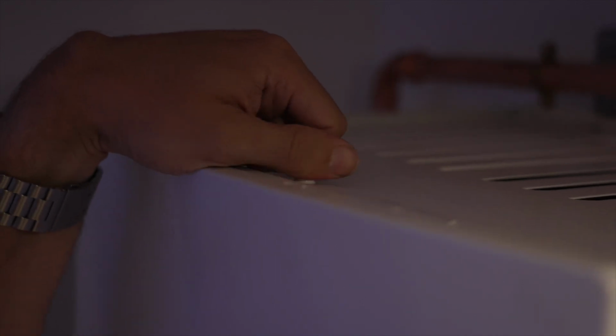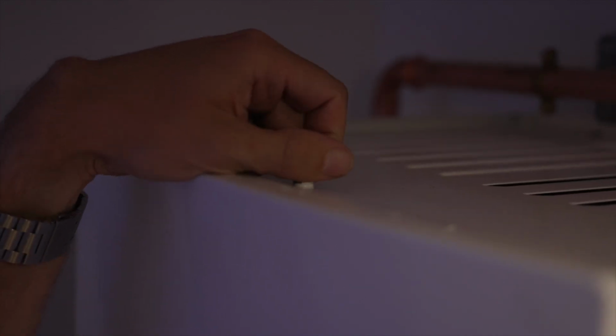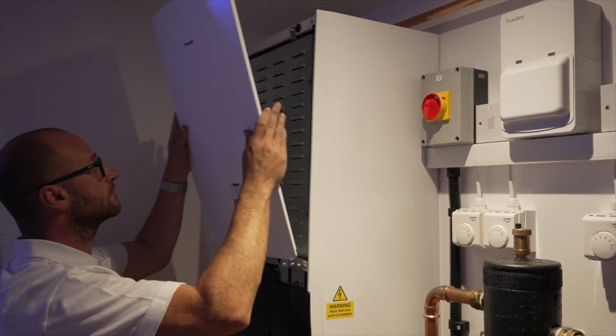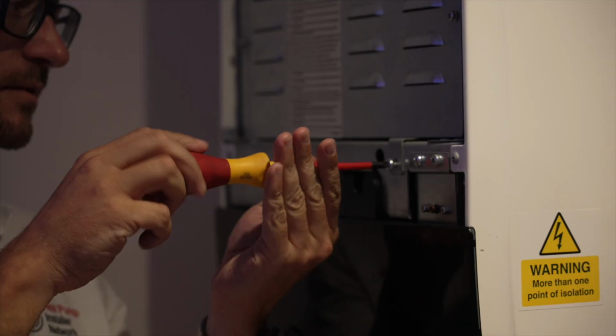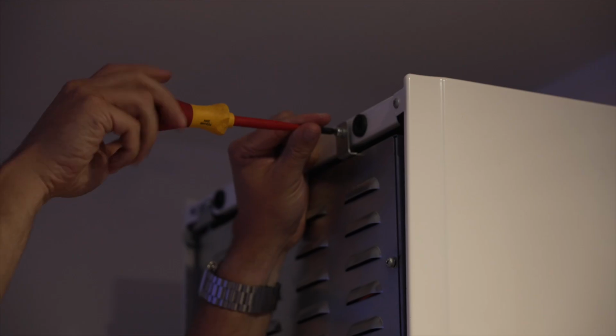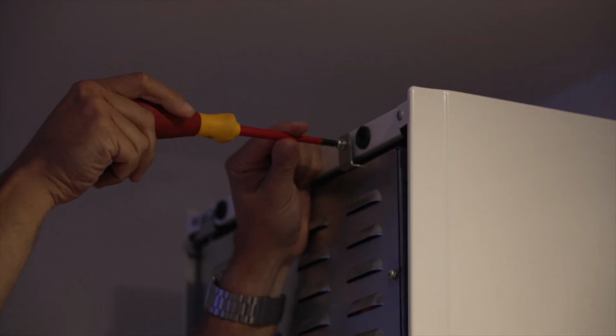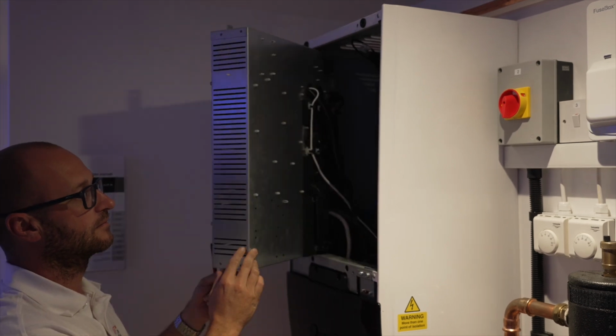Once it's installed, we can remove the front cover. There is a knurled retaining screw on top of the unit that should come undone by hand. If it's too tight, a posi screwdriver can be used, and now we can pull the cover forward and up to remove it. Once the cover's off, you will see the electrical switch box. We'll look in here when we get to the electrical section of the course. There are two screws, top and bottom, on the right-hand side that must be undone to enable this to hinge forward. This then gives us access to the hydraulic components.